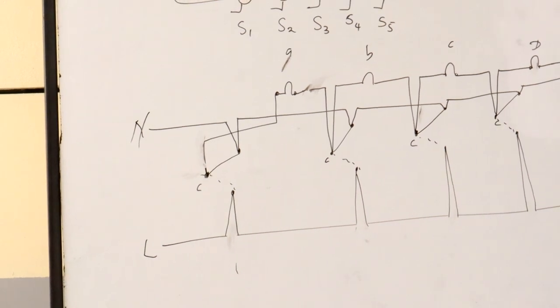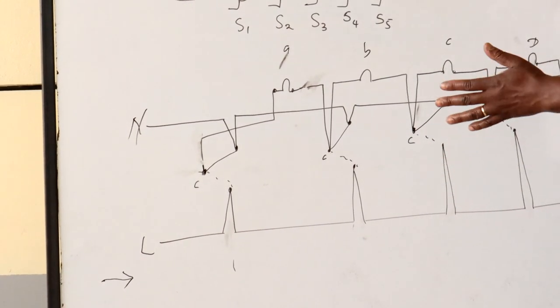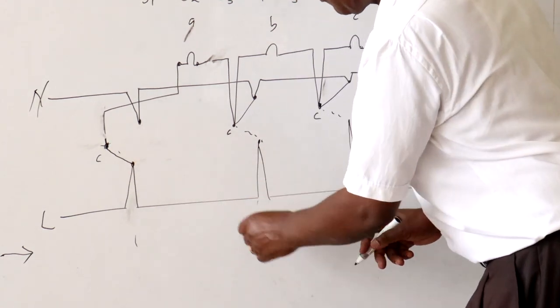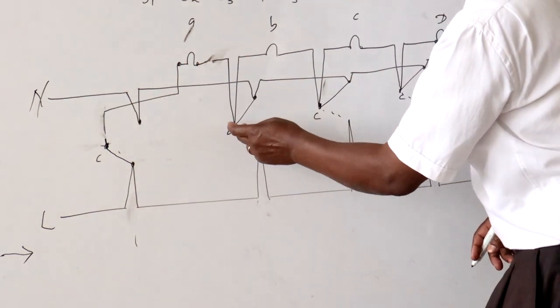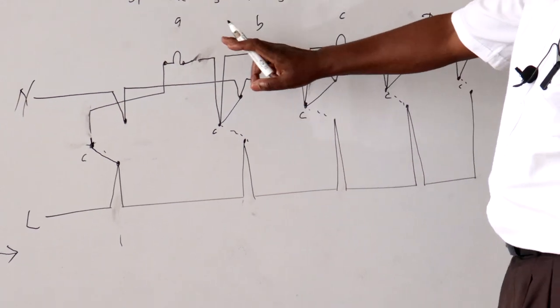Let's assume this is my live and that is my neutral. I'm going to assume we are coming down from this end. As you can see, all the lights are off — they all connect to the neutral pole. So once I get to the first switching position, I'll flip this one from that position to come down to that position. My live will come up through that lamp, back here and down to the neutral. So the first lamp goes on.